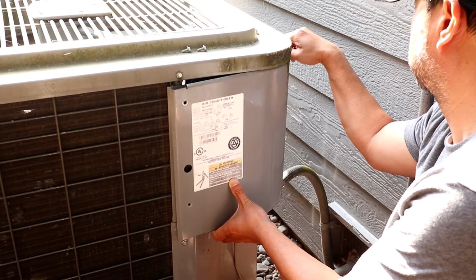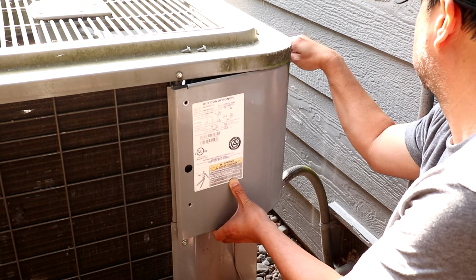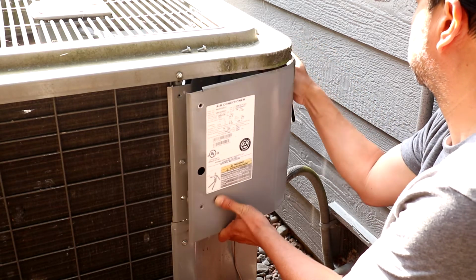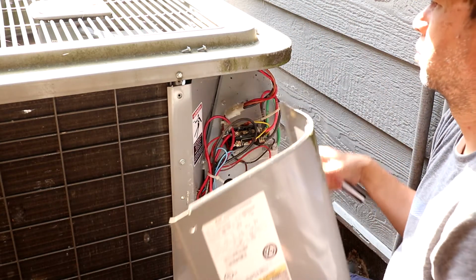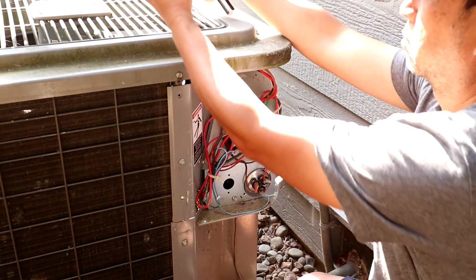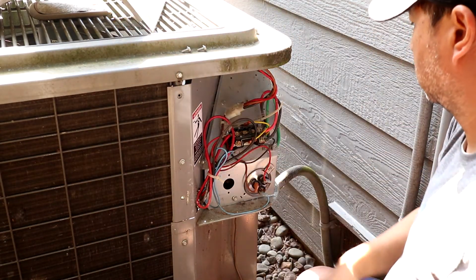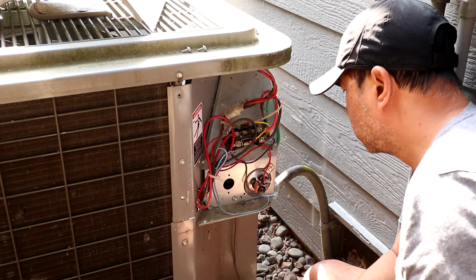I know power is shut off, but once the panel is open, I still need to be careful of any lingering electricities, especially from the capacitor. Even though I've had my power shut off to this unit for about a week, the capacitor can still hold a dangerous charge for a long period of time.